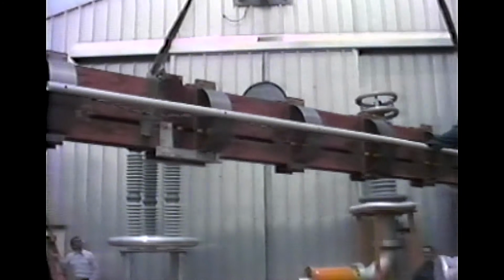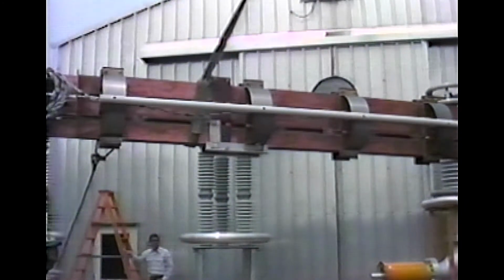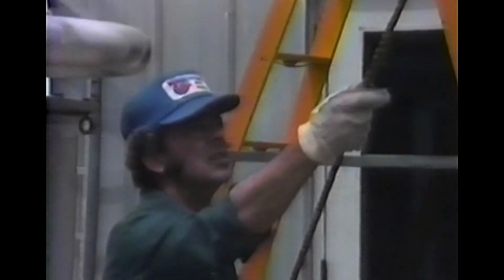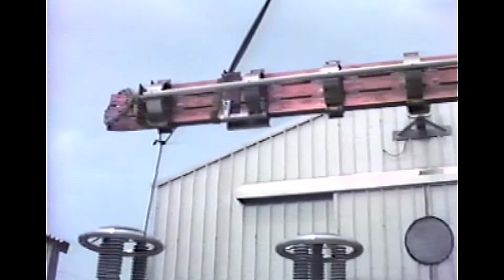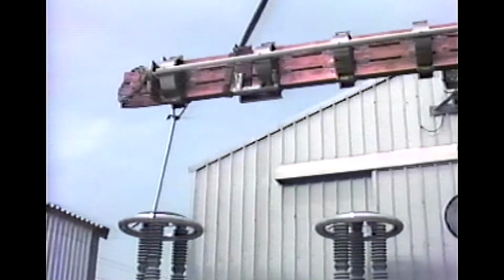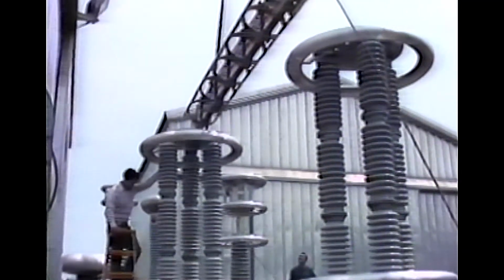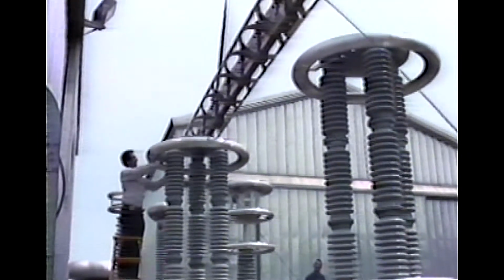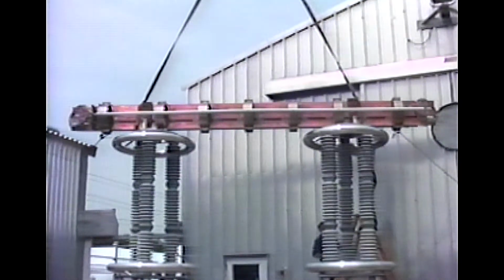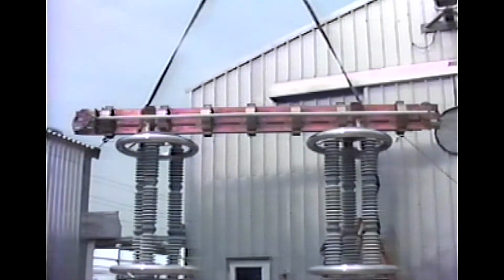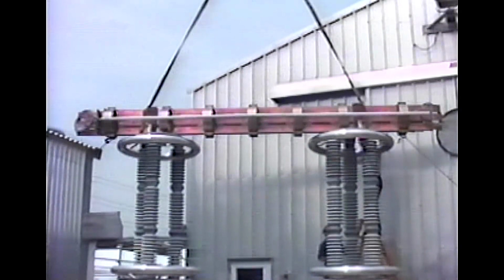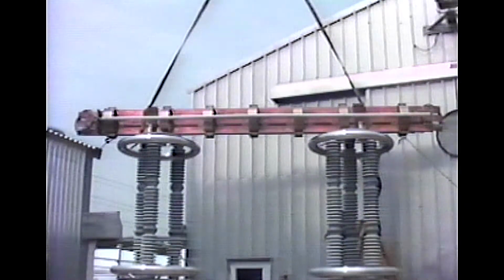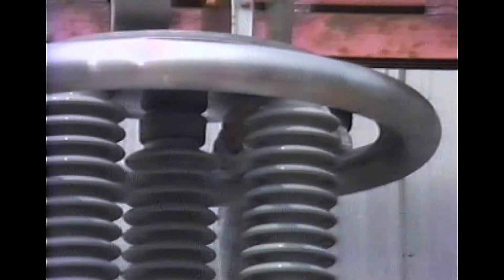Here, the copper bus bars which connect the power supplies to the west end terminations are being lifted into position on the insulated supporting stands. The size and weight of the bus bars, which carry the same current as the supraconducting cables, emphasize the amazing current carrying ability of supraconductors. The bus bars have a cross-sectional area about 400 times larger than the supraconducting tapes forming the cable conductor. These were seen earlier as the thin metal strips which were formed to complete the cable ends.